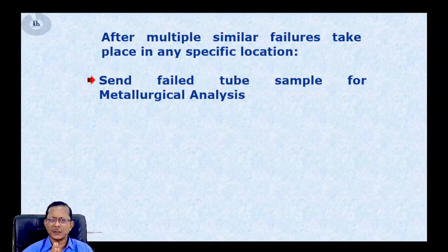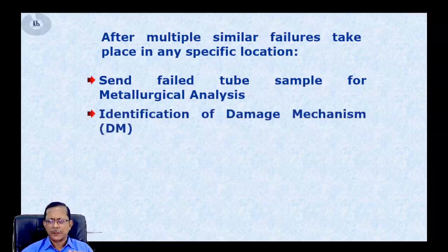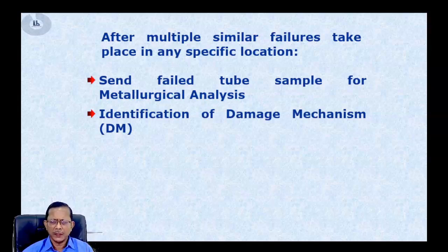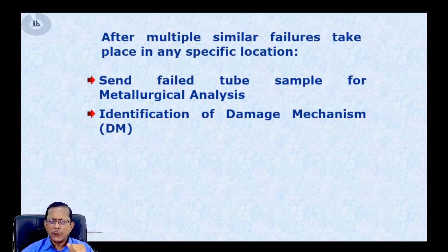The lab gives a report showing microstructure analysis, the original material metallurgy specification, whether it matches the OEM specification or not, and finally a conclusive identification of the damage mechanism — whether the tube failed due to erosion, corrosion, or overheating, and if overheating, whether it was short-term or long-term overheating.